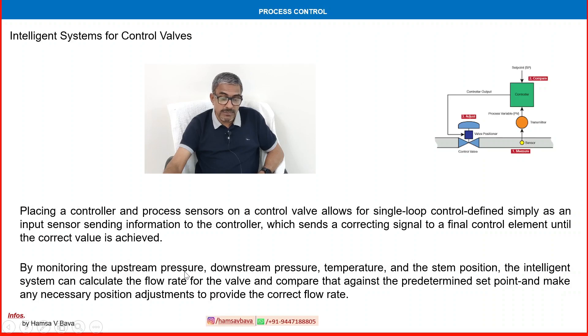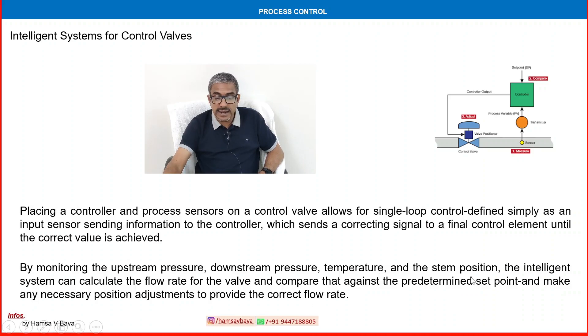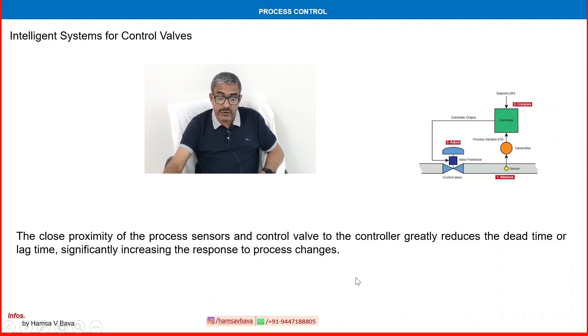Placing a controller and process sensors on a control valve provides a local control loop for single-loop control — an input sensor sends information to the controller, which sends a correcting signal to the control element until the corrective value is achieved. By monitoring upstream pressure, downstream pressure, temperature, and stem position, the intelligent system can calculate the flow rate and compare it against the predetermined set point, making any necessary position adjustment. The close proximity of the process sensors and control valve to the controller greatly reduces dead time and lag time, significantly increasing the speed of process response.